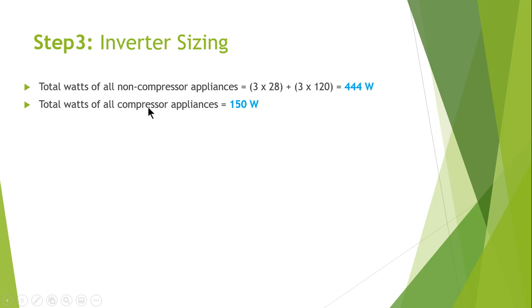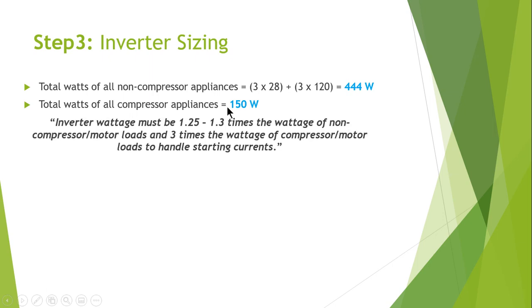The total watts of all compressor appliances is the refrigerator at 150 watts. When designing the inverter, keep in mind that inverter wattage must be 1.25 to 1.3 times the non-compressor motor load wattage, and 3 times the compressor motor load wattage, in order to handle the starting current.